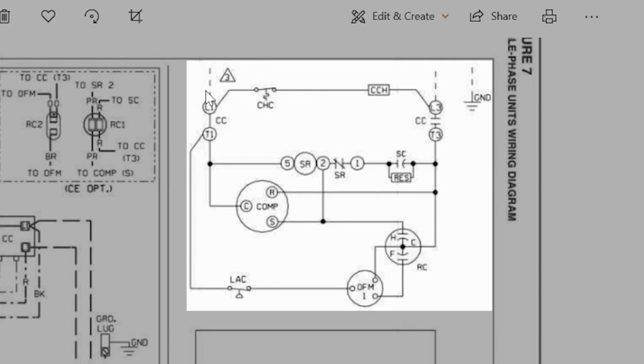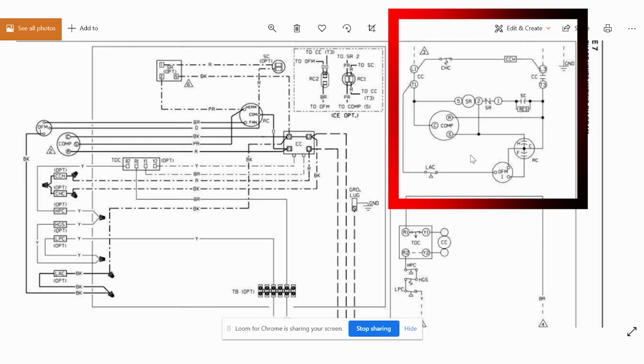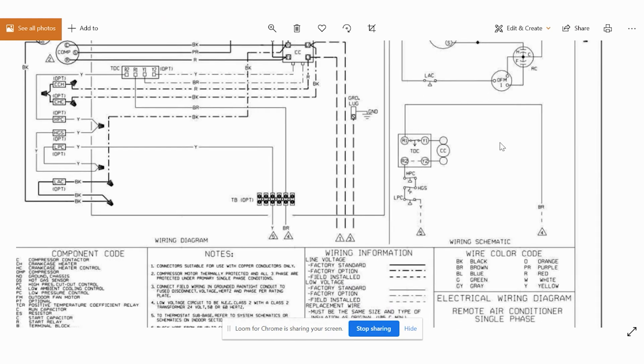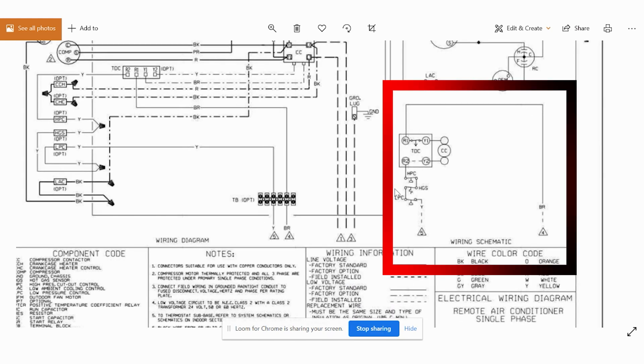And so a ladder schematic actually sorts everything in between the two sides of the circuit. So we talk about this all the time where current has to move in between two sides of a circuit. You can't have any opens. And so on this side, they're showing the high voltage side that could be present in the condenser. And then down below, they're showing the low voltage. And that's pretty standard.